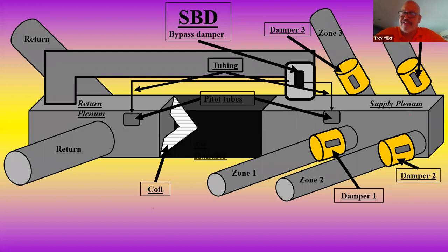Now, let's just say we push the button, it goes through its algorithm, and instead of the yellow light going out, the light continues to flash. This means that our bypass is too big. So we have to make some adjustments on the bypass to make it smaller. Look in the top right-hand section of your installation instructions, it'll tell you. You're going to go to the screw on the hash mark on the U-bolt. We're going to turn that and make the damper smaller, minimum open. So therefore, we've just gone from a 14-inch bypass to a 12-inch bypass. Push the button again, and then it should set up.